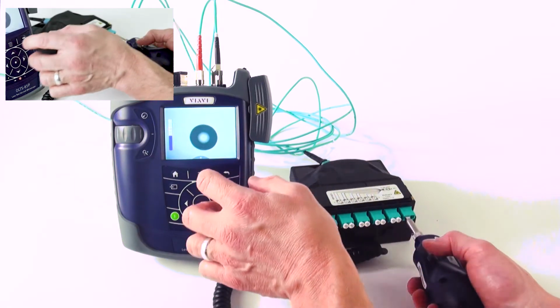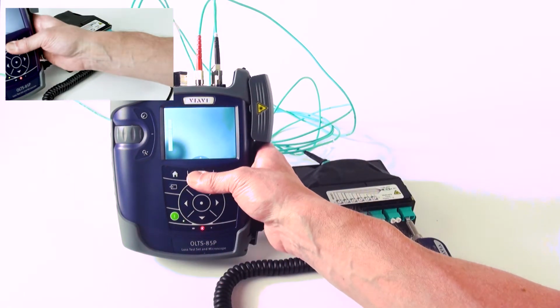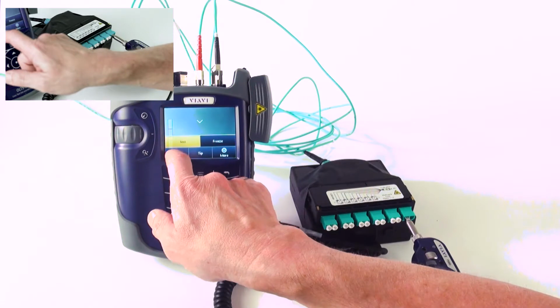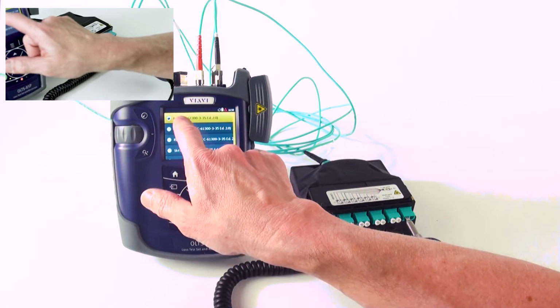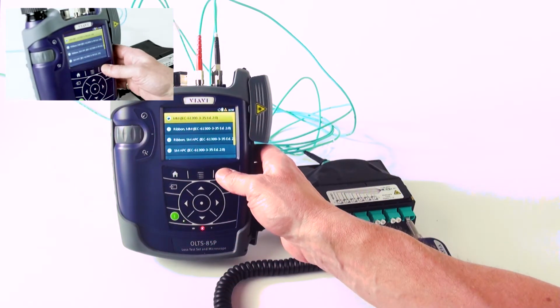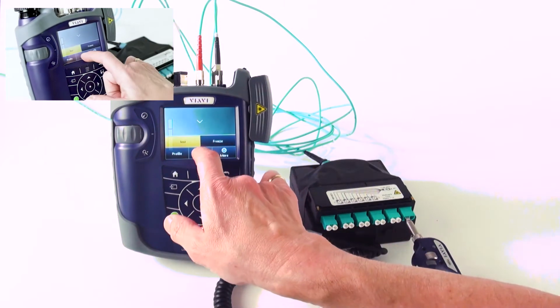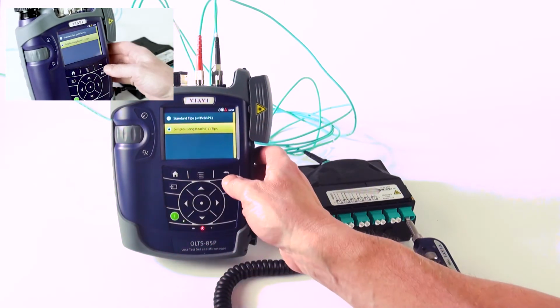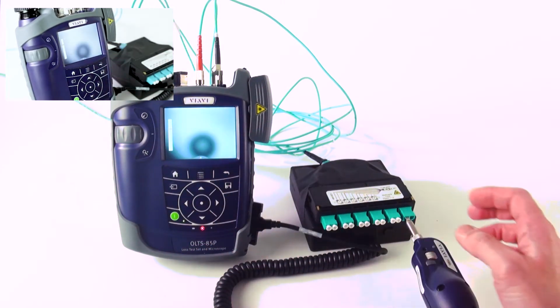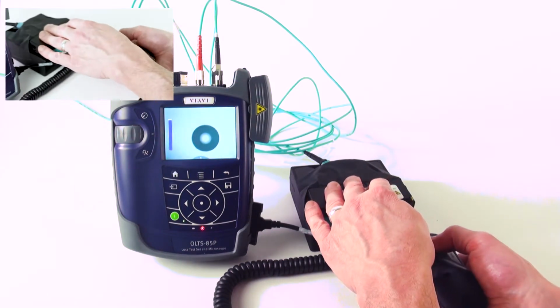Now, one of the things that I haven't shown that I maybe should show quickly is that I have to set my profile up for my pass-fail analysis to the multi-mode using the IEC standard, and I also have to set my tip up, and in this case I'm using a long reach tip, so I've set all that up. We have other videos on fiber inspection that cover this in a bit more detail.